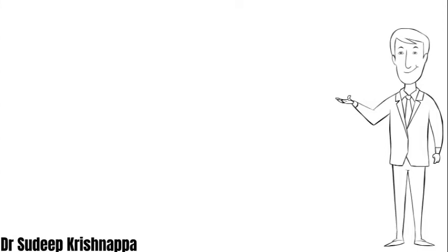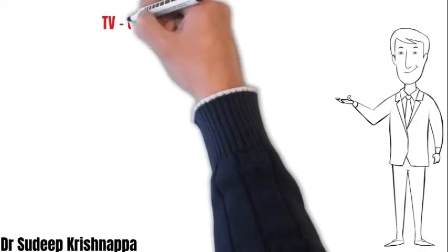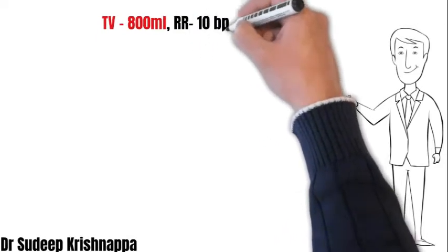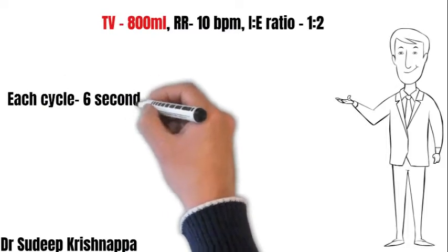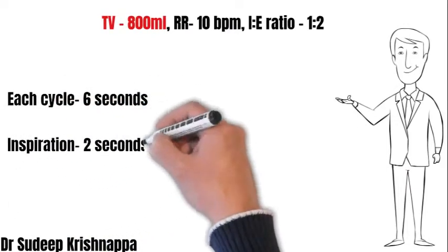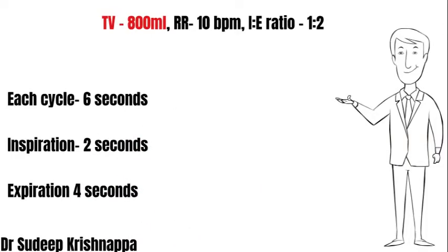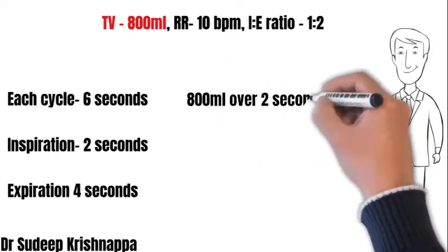Moving on to the second scenario: we change the tidal volume to 800 mL, keeping the respiratory rate and I:E ratio the same. Each cycle remains 6 seconds with inspiratory time of 2 seconds and expiratory time of 4 seconds. The tidal volume of 800 mL must be inspired over 2 seconds, translating to a flow rate of 400 mL per second.